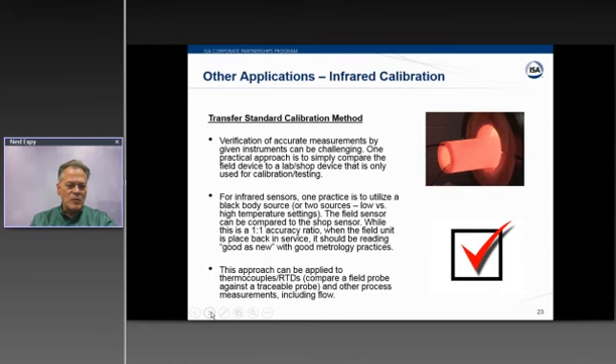And specifically for infrared, one way to simulate temperature is, instead of a dry block like Roy's been using, you can get hold of what's called a black body or a black body source. And ideally, it would be nice if you had 2 black bodies. You could set one to a low temperature and just let it sit there, and then set the other one to a higher temperature that represents your process and let it sit there. So it's always soaked out, reading a consistent temperature. So then for this type of test, you would remove the field sensor, bring it to where your black body is, and aim it at the black body. You would have your shop standard also pointing, and you'd be able to do a comparison of the temperatures.